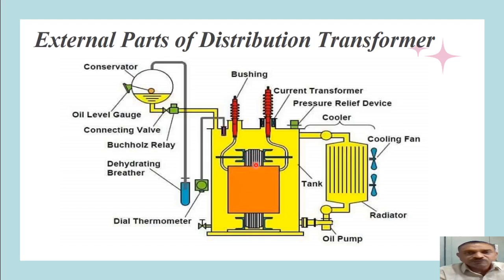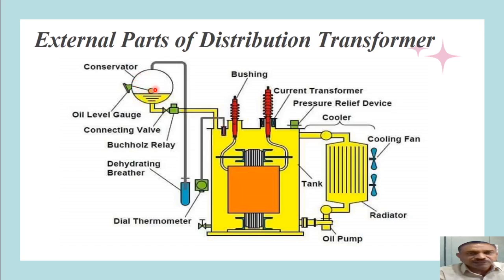These losses raise the temperature of the oil, causing it to expand. The conservator tank provides a provision for this expanded oil. When oil expands, its level in the conservator increases, and we can observe the oil level using the oil gauge fitted on the conservator tank. When the transformer operates at no load or reduced loading, less heat is produced, temperature is lower, expansion is reduced, and the oil in the conservator goes back to the main tank.